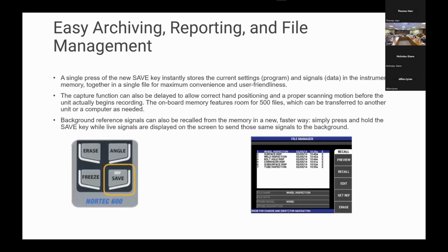A single press of the new save key will instantly store the current settings and signals in the instrument's memory together in a single file for maximum convenience and user friendliness. The capture function can also be delayed to allow correct hand positioning and proper scanning motion before the unit actually begins recording. Onboard memory features room for 500 files, which can be transferred to another unit or to a computer as needed. And then background reference signals can also be recalled from the memory in a new, faster way. Simply press and hold the save key while live signals are displayed on the screen and send those same signals to the background.